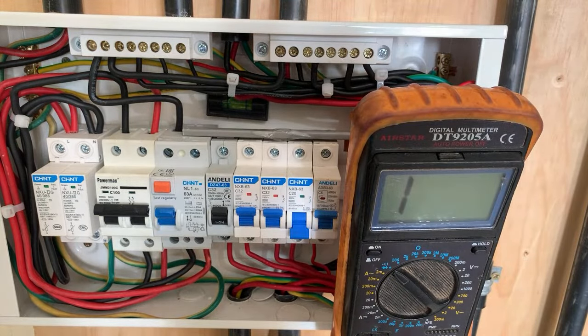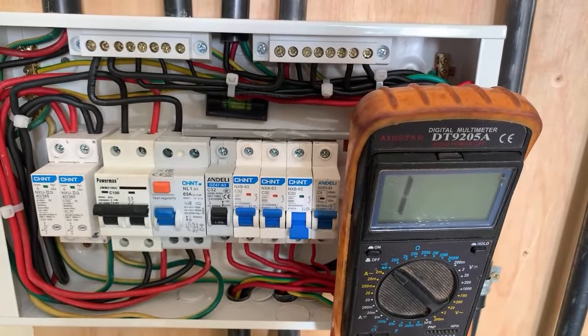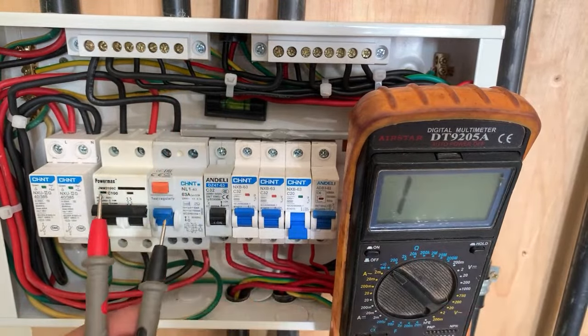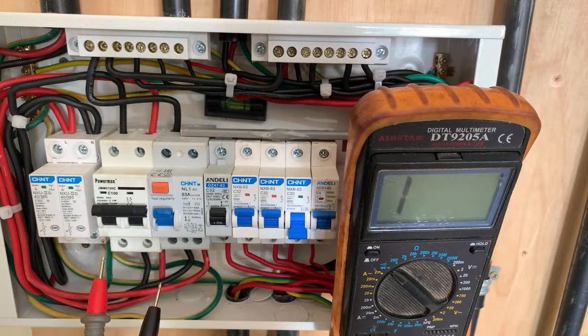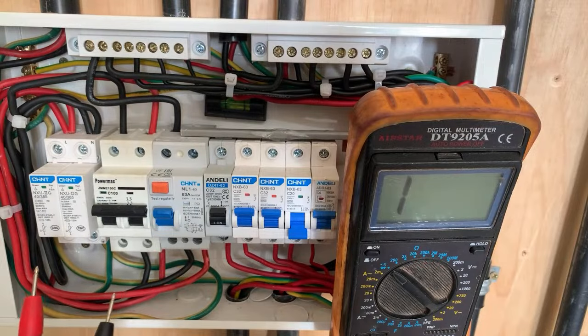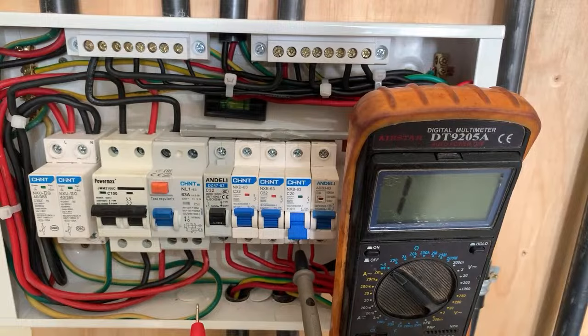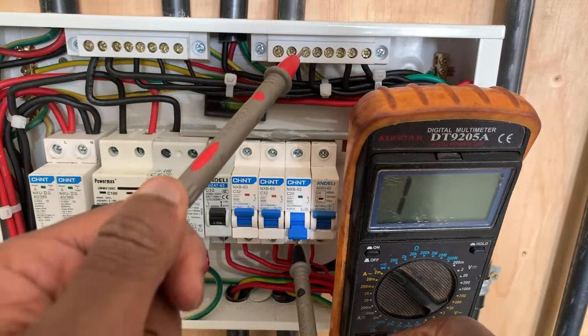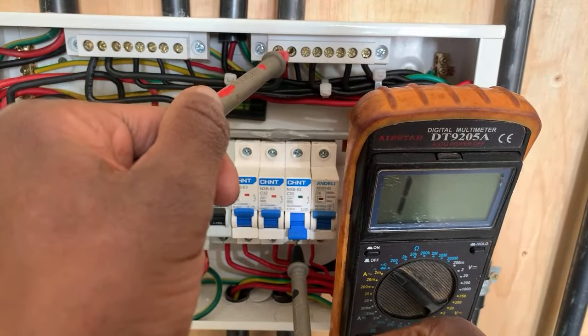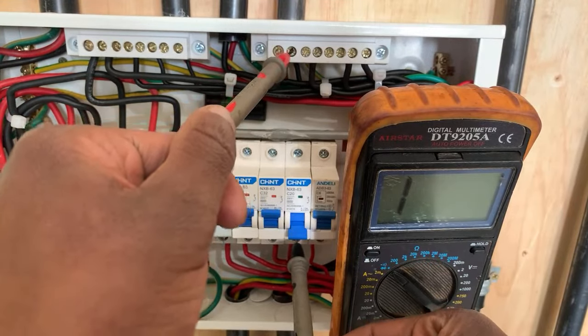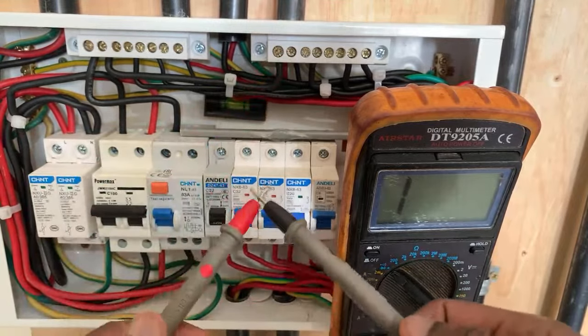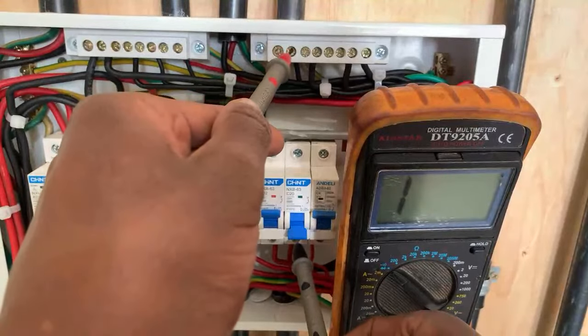And if the socket is not damaged, what you will need to do is to simply take your meter again. You are not done with our meter, because that is a very important thing for an electrician to have, like I said. If you only have your tester, you will not get a lot of help from your tester, or from the pliers or the few appliance tools that you have. So you still come here, take your probes and connect there. If you are not getting a beep, then the circuit is resolved. That issue with the socket has been resolved, and so your circuit is okay. It is open, there is no problem.